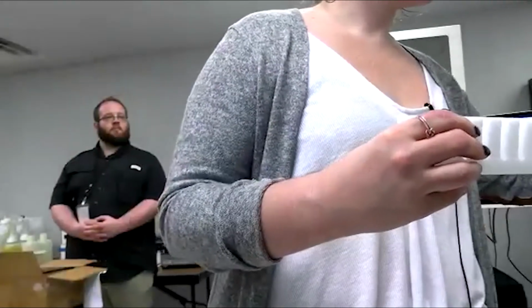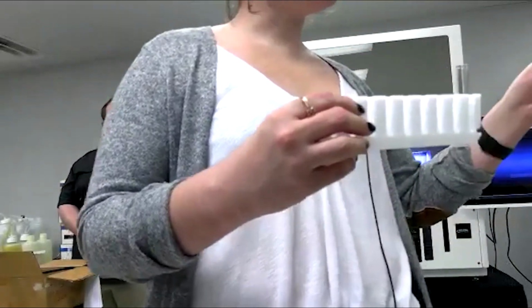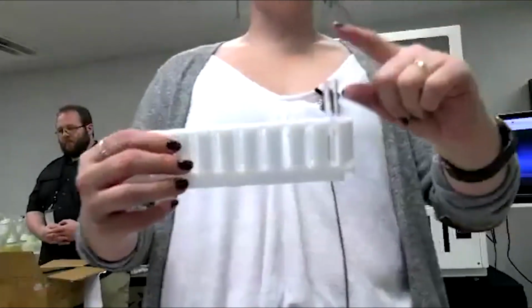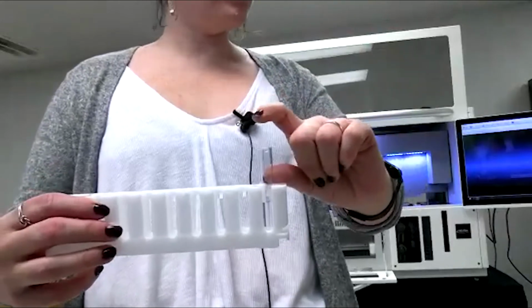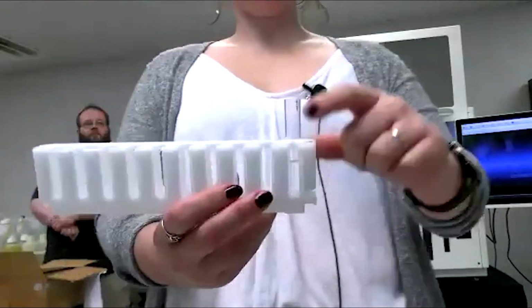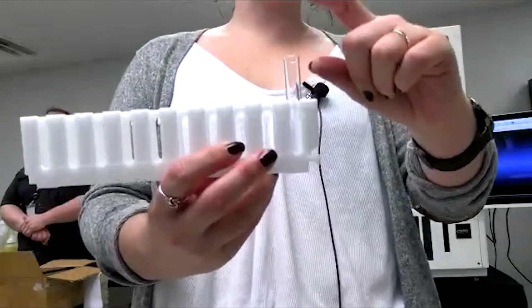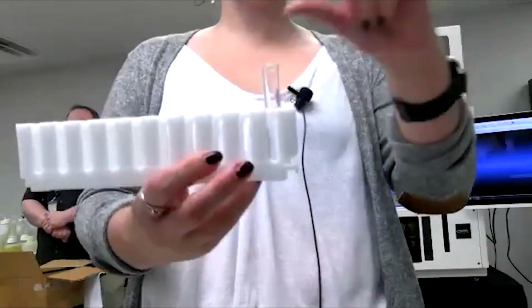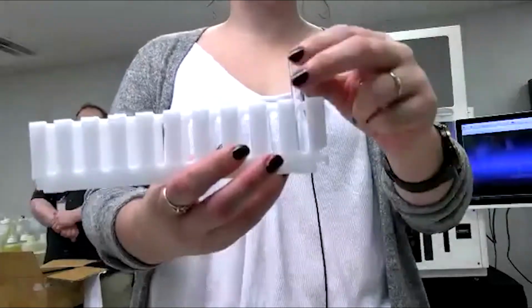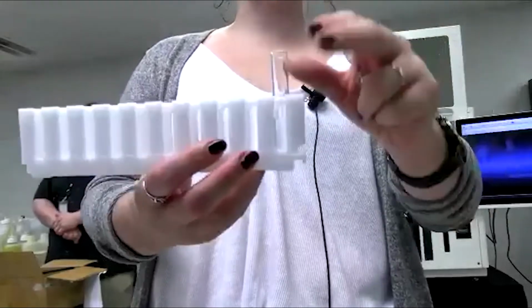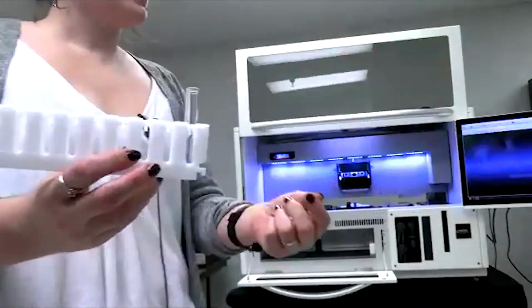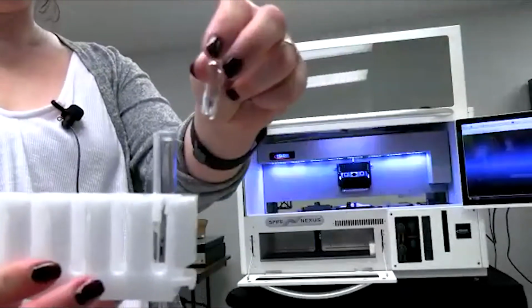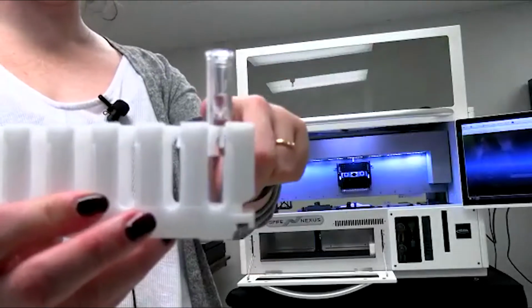Yes. And do you have any of the bigger 16 millimeter tubes? So there's also another standard size of tube that's about this much taller. That's usually the largest standard tube that's used. There is one bigger jumbo tube that doesn't fit in our machine, but for the most part, the 2 most standard sizes of tubes you will be able to use with this. Just have the smaller inserts, not bigger. Oh, there we go. We do have nesting cups that fit in the top, and it can sample from the nesting cups. Is this the type of thing you're talking about? Oh, no. But I'm going to make note that a nesting cup is okay and it fits into the tube.